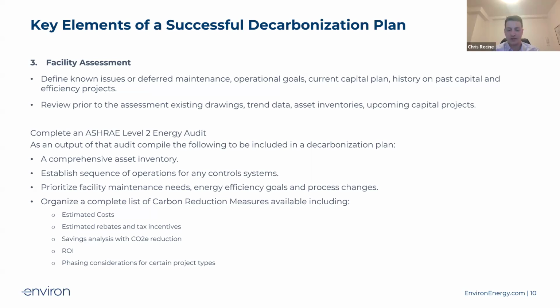Do you have the breakers available or the panel schedule available to support that project? Do you have the redundancy? Because if you're switching typically from natural gas, fuel oil was your backup. So now you need to add generator capacity to potentially decarbonize. Healthcare has an interesting problem where there's a cascading effect if you really do want to fuel switch and move to an electric-based system, there are extra hurdles to overcome. Where you put the generator and the physical requirements of that system can sometimes be no easy task in a healthcare logistics organization.